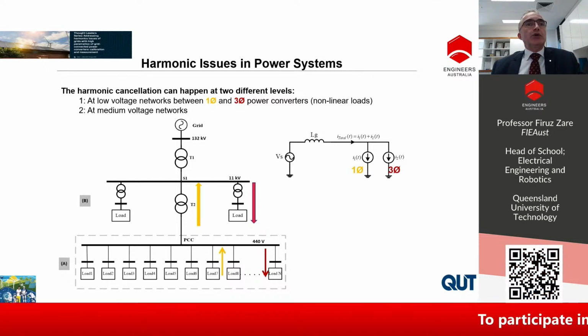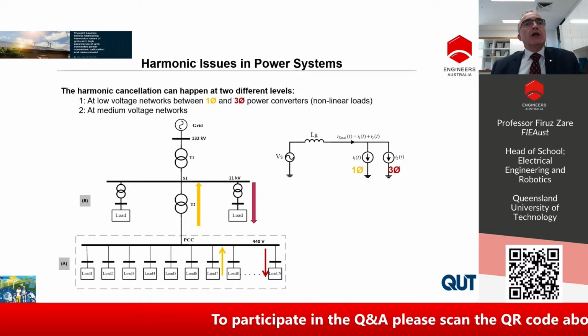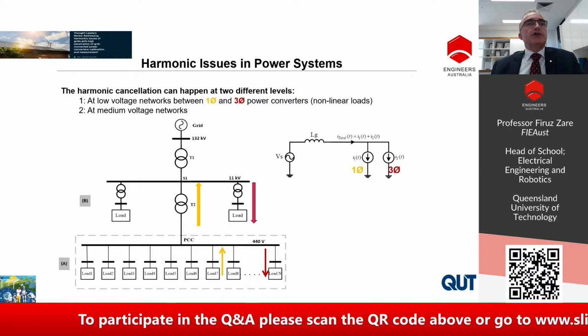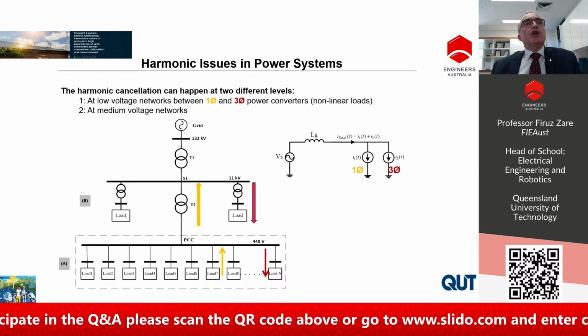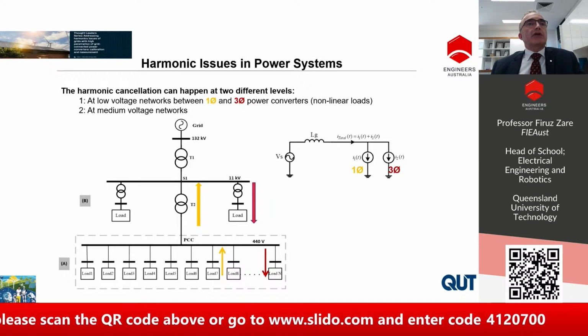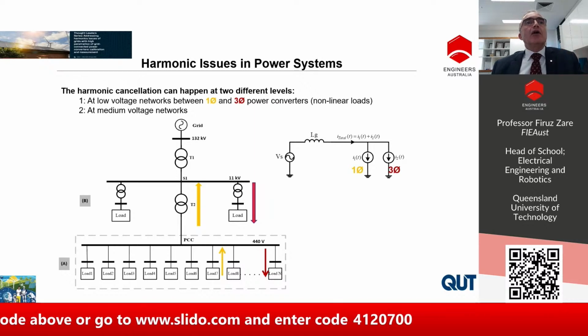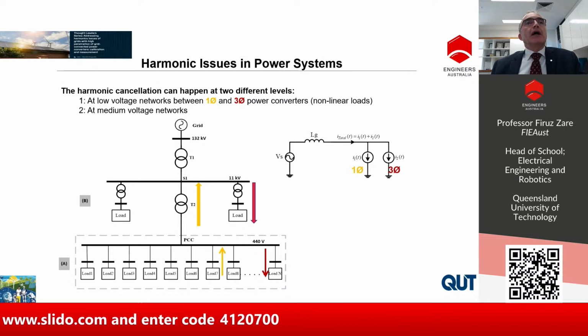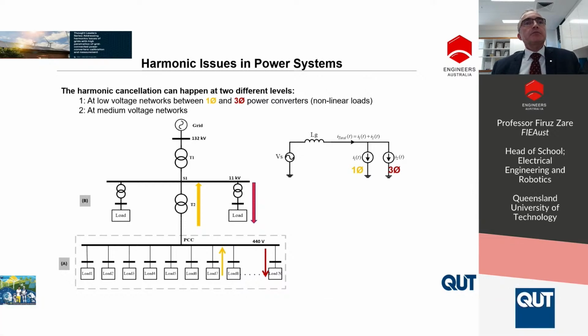From the utility point of view, the power quality of the voltage at medium voltage is important. Because of the combination of commercial, residential and industrial sectors, some of the single-phase power converters, with a different phase angle of their harmonics, can cancel three-phase devices with almost opposite phase angles. That's why we expect that harmonic cancellation can happen in the network, especially at medium voltage. That's one of the reasons that we have different types of regulations and standards for grid-connected inverters.